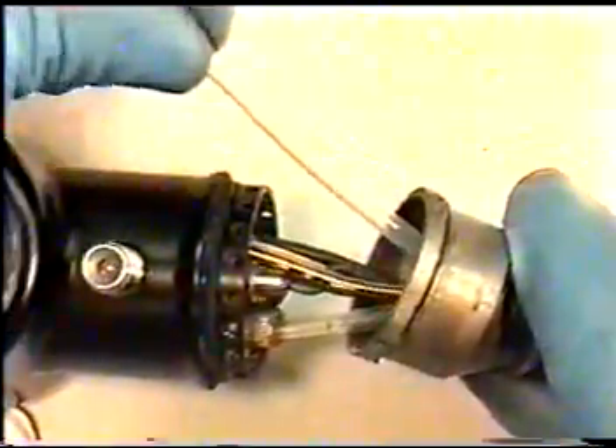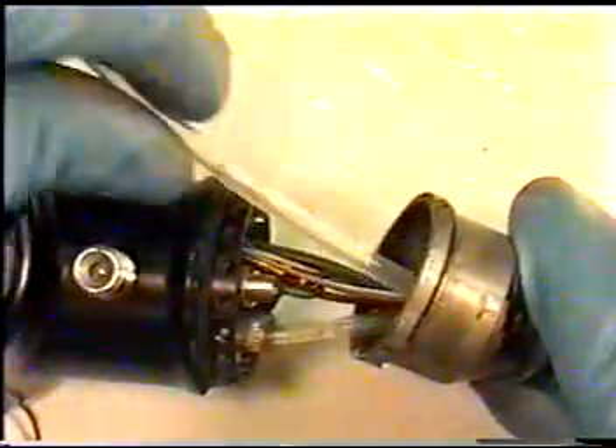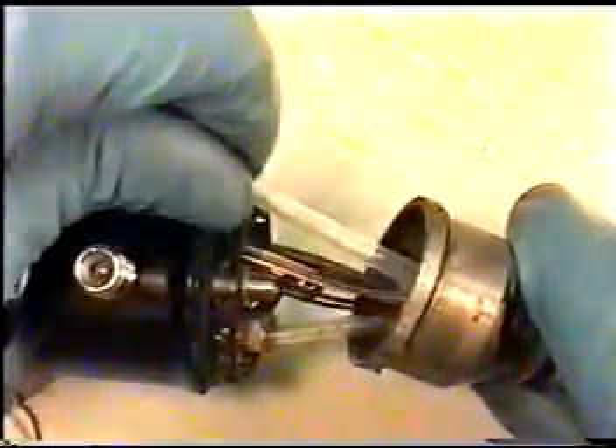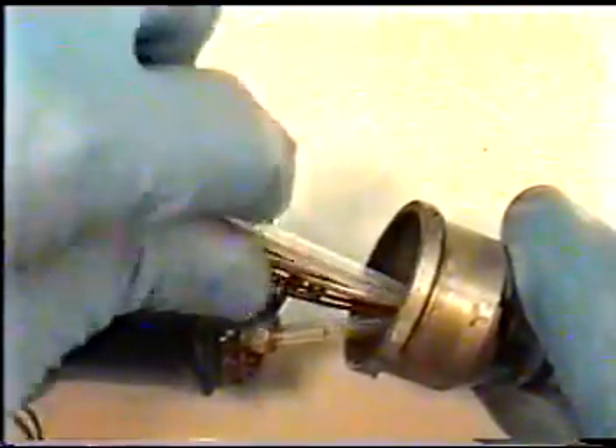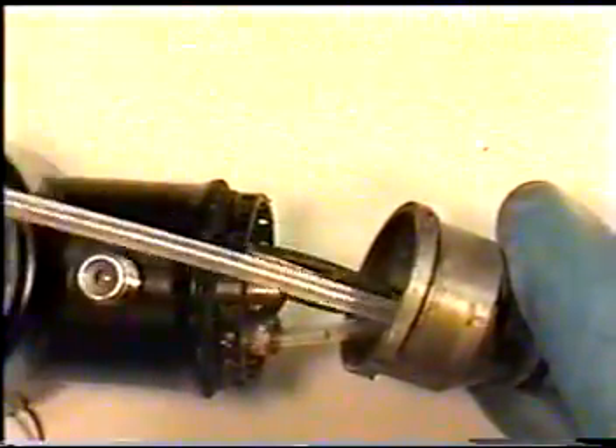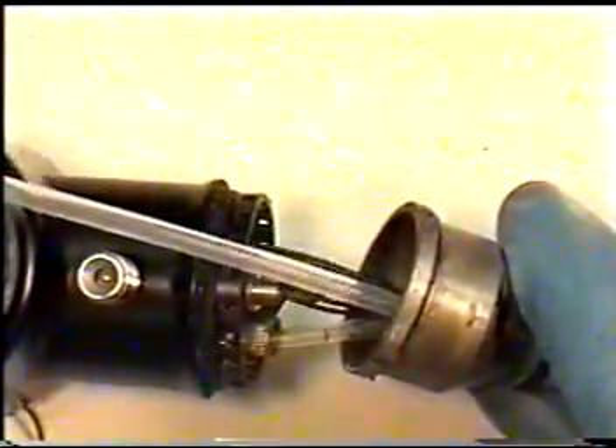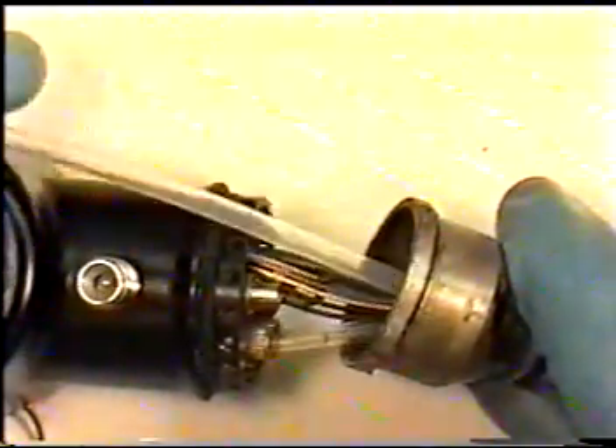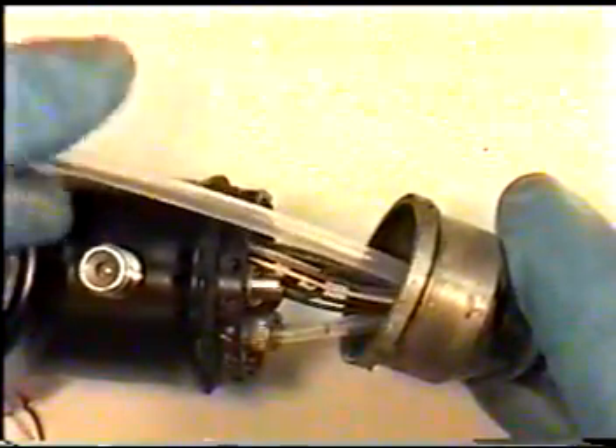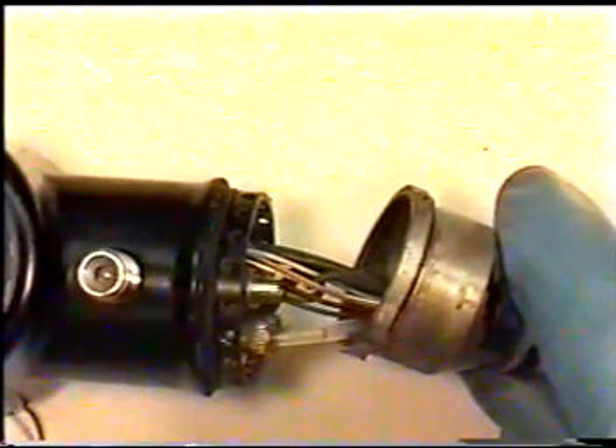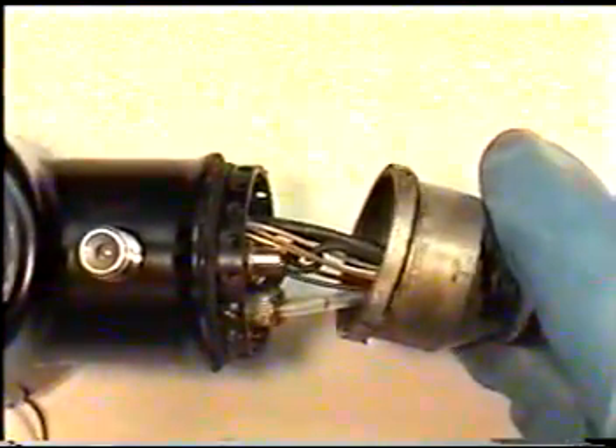We can now slide out our suction tube from our umbilical section in order to remove our light guides and replace them with new ones. Remove the suction channel completely. Discard the suction channel. You need to replace it with a new one. Since we have cut it in the body section, it will be no longer useful and will need to be replaced with a new suction channel.